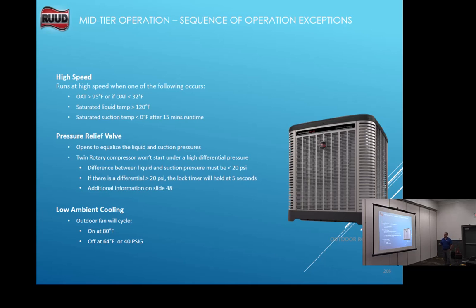That's because on that outdoor stat, if it sees above 95 degrees, or if it's a heat pump, if it sees below 32 degrees, it's automatically going to go to high speed. Nothing I can do about it. That's in the demand-based logic that they've built for the system. Some kind of fixes for the outdoor part of it was the sun was shining right on the unit, so contractors made a little shield or took that outdoor temperature stat and moved it around to the shade, so it didn't run in high speed all the time. Okay, when that temperature got up and that sun was blazing down on it this past summer.